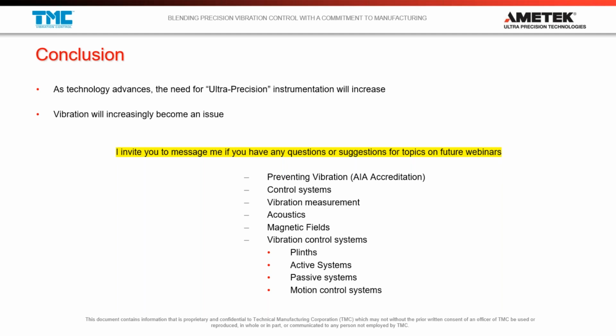But if you go down to the basement of that building, you might see no horizontal, but the building sway above might generate that drumhead effect that I was talking about, and you might see a strong vertical issue due to the horizontal sway of the building. So a lot of that has to do with building construction and where you're located in the building. So I'm sorry, there's really no good way to say which one's often higher amplitude. But thank you for your question. Okay. I hope I answered. Yeah, so we need to measure.